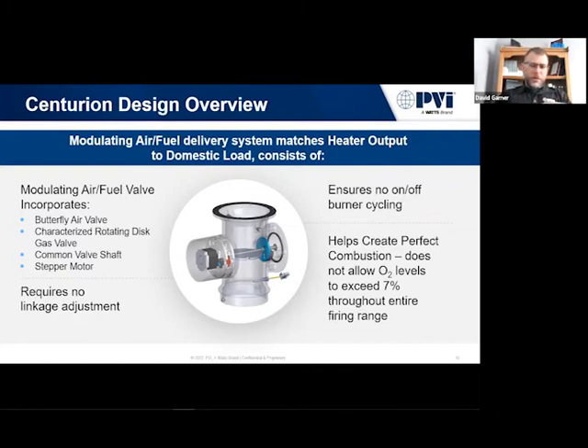We could do 20-to-1 turn down just with this valve and having the blower on off. That's not very efficient from an electrical standpoint. So the blower ramps up and down with this valve opening and closing, and it's going to maintain the O2 levels right where they need to be to make sure we have a good solid flame and we don't have excessive O2 levels, which I'll talk about here in a second.